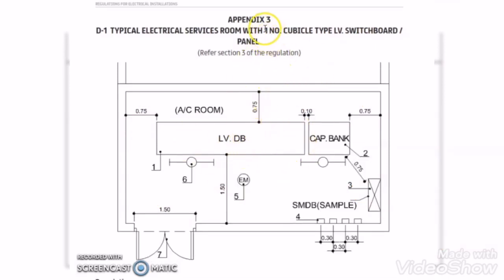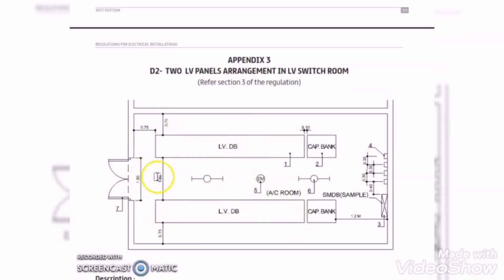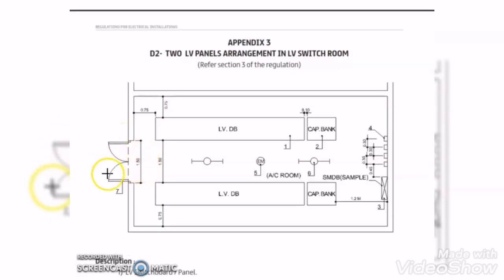We discussed the case of one LV panel inside the LV room. Now let us discuss when there are two LV panels inside one electrical room. As in the previous case, the back side wall of each panel and the back side wall of the electrical room must be 0.75 meter apart. The panel-to-panel distance must be maintained at a minimum of 1.5 meters. The minimum width required for the LV room is 1.5 meters. If we are placing a capacitor bank adjacent to the LV panel, the minimum distance between the two panels must be 10 cm.